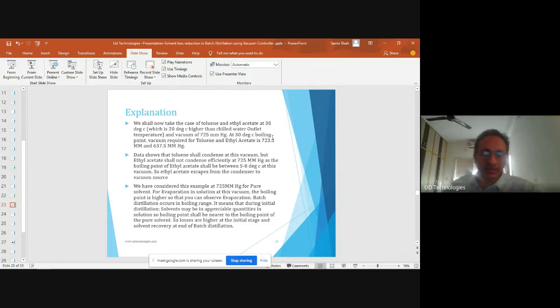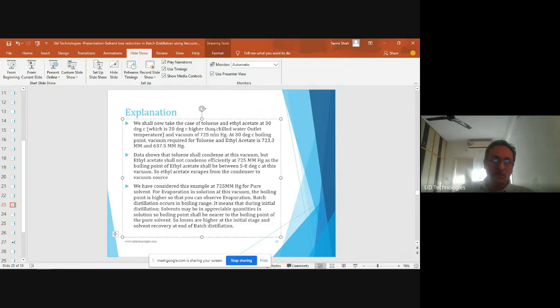We shall now take the case of toluene and ethyl acetate at 30 degrees centigrade, which is 20 degrees higher than the chilled water outlet. Vacuum is around 725 mmHg. At a 30 degree boiling point, the vacuum required for toluene and ethyl acetate is different, that is 723.3 and 637.5 mmHg. The data shows that toluene shall condense at this vacuum, but ethyl acetate shall not condense efficiently at 725 mmHg, as the boiling point of ethyl acetate shall be between 5 to 8 degrees centigrade at this vacuum. So ethyl acetate escapes from the condenser to the vacuum source.